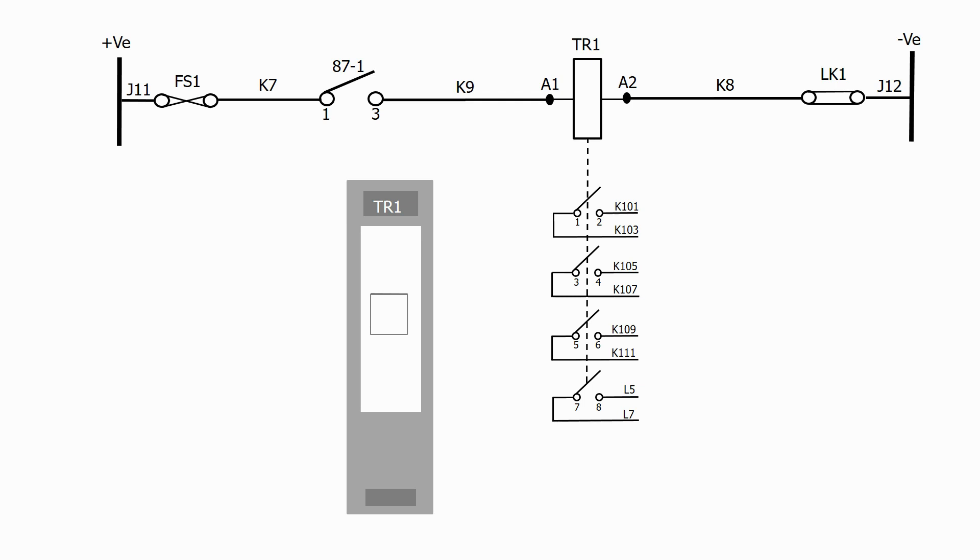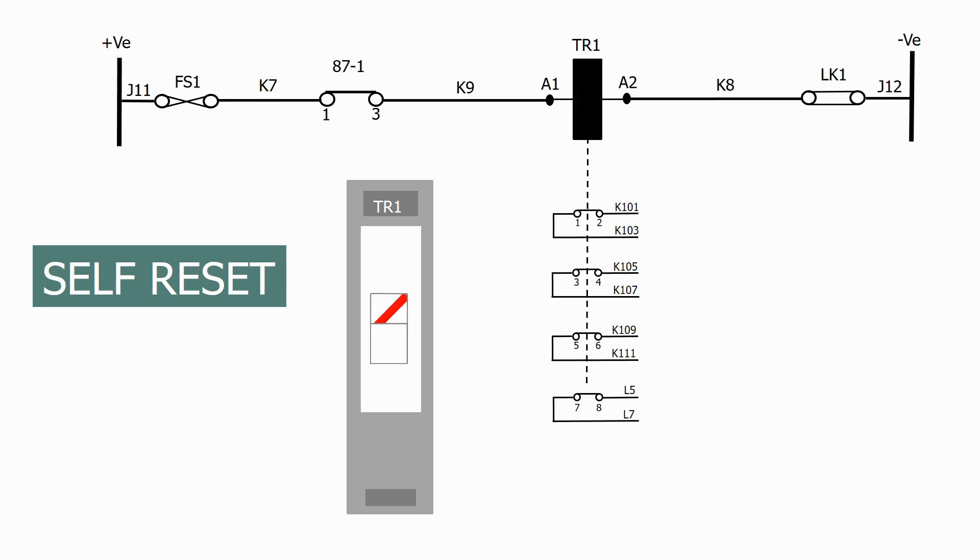The first option is a self-reset flag. In this configuration, when the relay coil is energized, the flag operates and the contacts change state. As soon as the initiation is removed, the coil de-energizes and the flag and contacts return to their original state, hence the name self-reset flag.